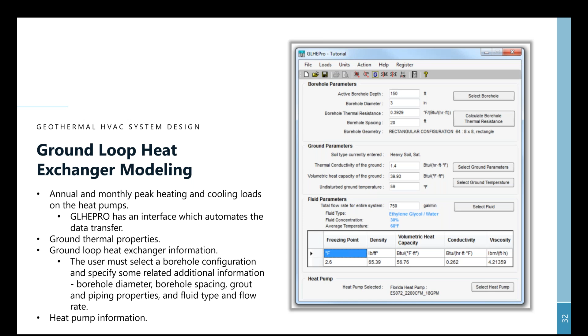So here you see two examples of the information that you can input for the borehole configurations. The top is showing the traditional single U-tube type borehole, but there are also options to do what we call a double U-tube, which, like the name implies, doubles the number of circuits in each borehole. Now, why would you want to do that?